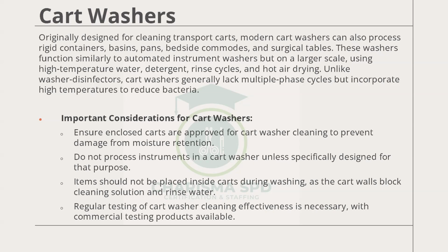So you see that temperature is one of the basic factors in our cleaning. The considerations here are to ensure enclosed carts are approved for cart washer cleaning. Do not process instruments in a cart washer unless specifically designed for that purpose, which goes back to the IFUs. Items should not be placed inside carts during washing, as the cart walls block cleaning solution and rinse water. That's easily understandable. When you go in there, you look at how the stations and the washers are built. You should not put items inside carts during washing.